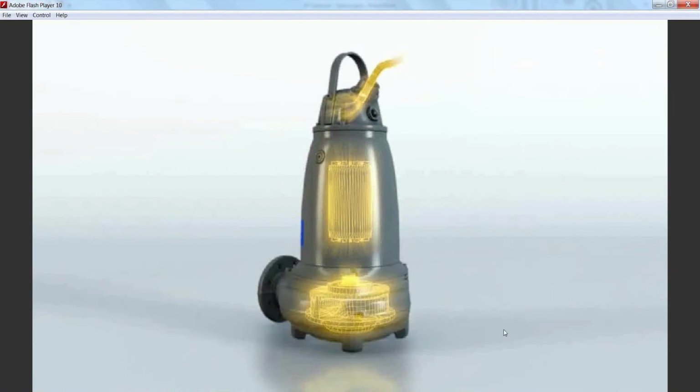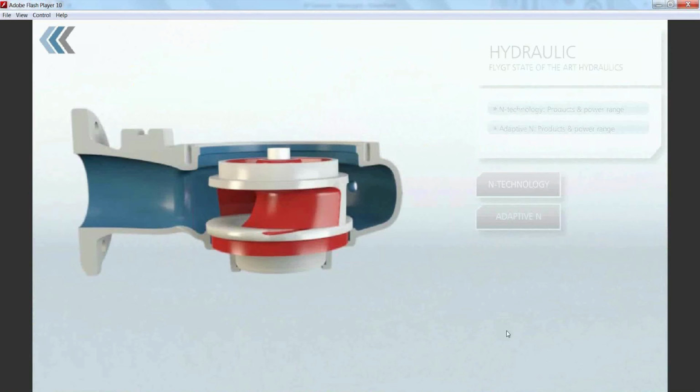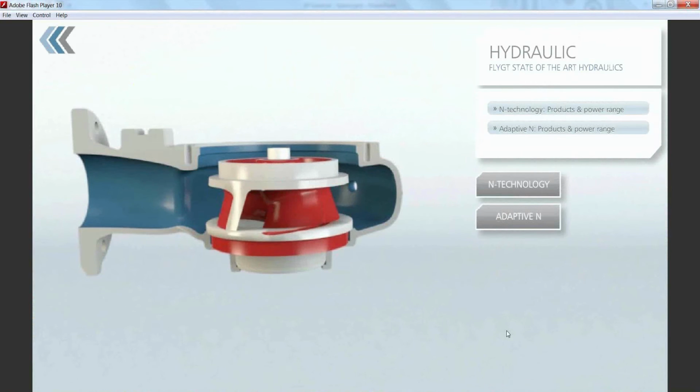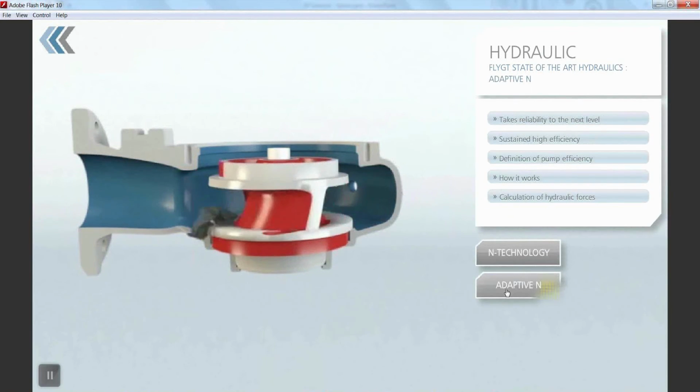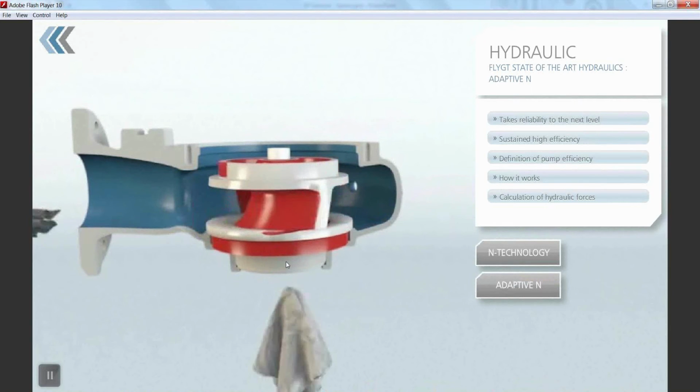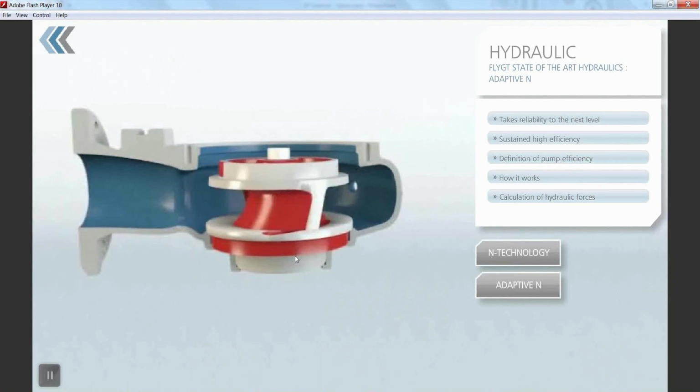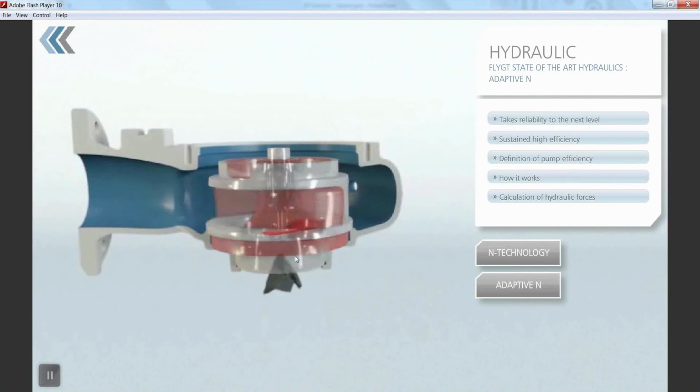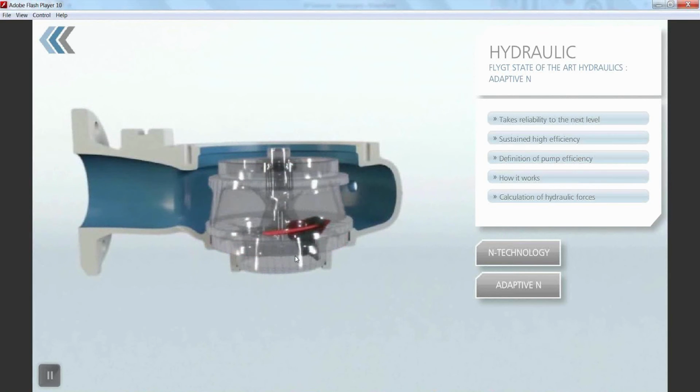So moving on to the hydraulic side. What we've done at Flygt is we've realised that we're using the Smart Run, we're using VSD, essentially slowing the pumps down. What we need to do is find efficiency, so we've changed our impeller design. With the new impeller, we're getting around 80 to 70% total efficiency, which is very good for a sewerage pump. Typically you'd probably be looking at around 65% efficiency on most other impeller types.